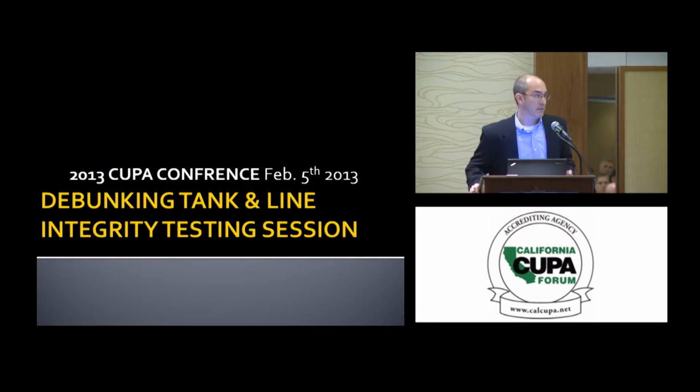Because it's an underfill test method, it would have to be followed up with an ullage test. The one we use is called the U3 ullage test. It's a non-volumetric and acoustic-based test. It can be used either with a vacuum or with pressure to detect any leaks in the ullage or the non-wetted portion of the tank.